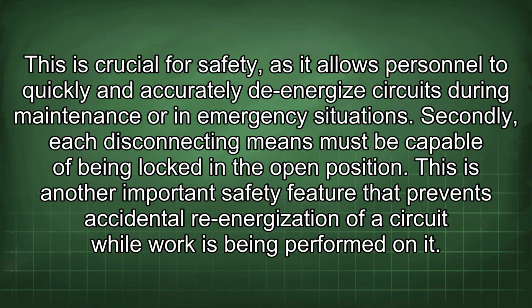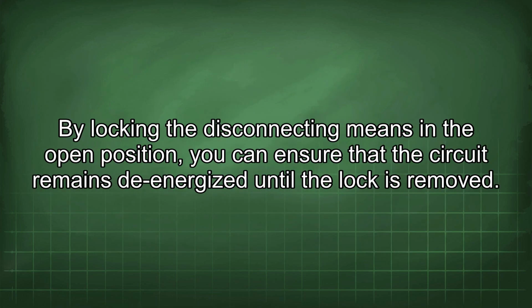emergency situations. Secondly, each disconnecting means must be capable of being locked in the open position. This is another important safety feature that prevents accidental re-energization of a circuit while work is being performed on it.